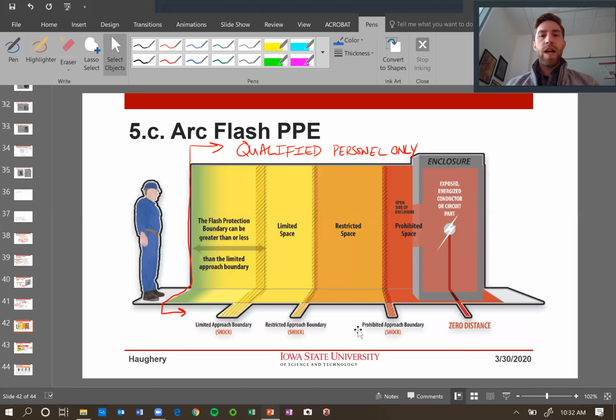And then of course, arc flash and PPE. As you turn on or connect any type of switch, there's going to be an arc as those two contact points get closer to each other. This actually happens every time you plug a cord into an outlet. There's a little spark. Of course, it's inside, so you can't see it, but the bigger the piece of equipment, the bigger that spark's going to be. And so we have safety PPE to protect humans as they are close to those environments.